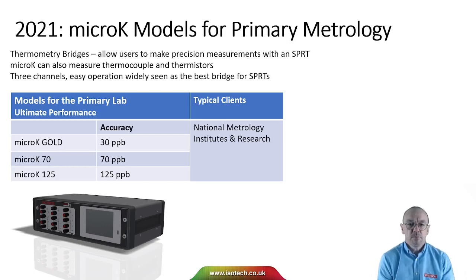So we have different models. With a thermometry bridge we can make these precision measurements with an SPRT, but the MicroK can also measure thermocouples and thermistors. We've got 3 channels, and it's widely seen as being the best bridge for SPRTs. So our higher performing models, MicroK Gold, 70, 125, typical clients for those are National Metrology Institutes and research. We can get an accuracy of 30 parts per billion over the whole range, better at specific ratio values.